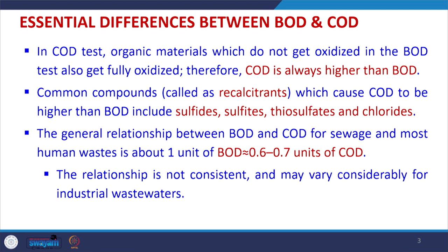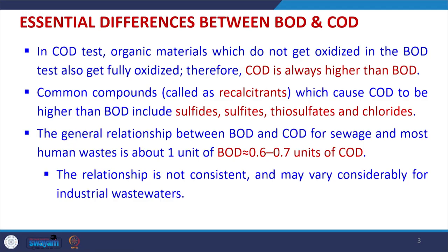Common recalcitrant compounds — those that resist biodegradation by microorganisms — cause COD to be higher than BOD. These recalcitrants include sulfides, thiosulfates, chlorides, etc. The general relationship between BOD and COD for sewage and most human waste is that 1 unit of BOD is approximately equal to 0.6 or 0.7 units of COD.